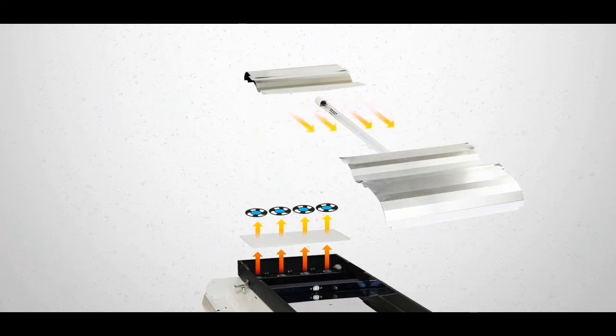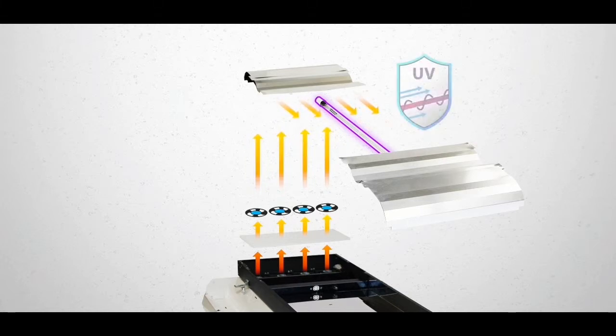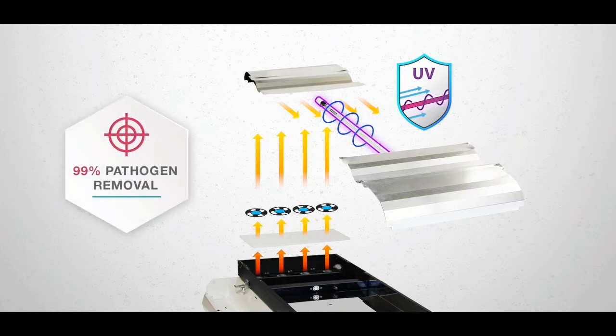The air now moves through a set of safety baffles which prevent the UV light from escaping the radiation chamber. Once in the radiation chamber our high intensity UVC lamp operates at the peak wavelength of energy emission at 253.7 nanometers. The duration and intensity of the UVC provides up to 99% pathogen removal with a 97% first pass kill rate.